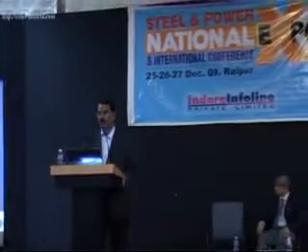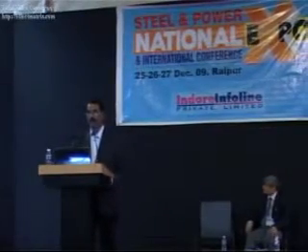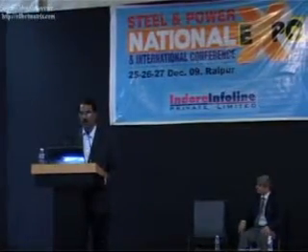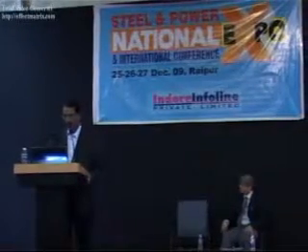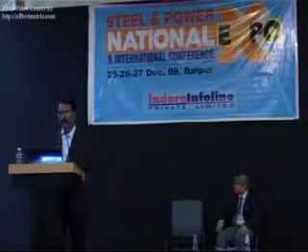There is another system which is also utilizing the closed cooling water. This is called machine cooling water system. This is an area where various types of machines, which include pinch roll, heat exchanger equipment, various types of hydraulic fluid coolers, water jacketed pumps, valves, need to be cooled, and a very high degree of water quality is required.